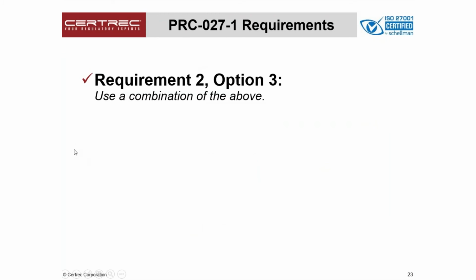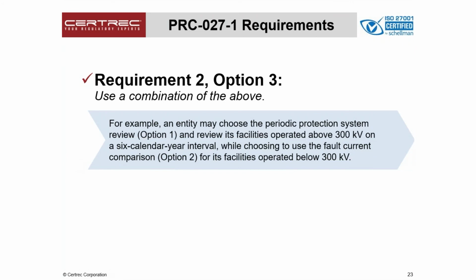Option 3 is to use a combination of the above. So this is an example out of the standard. You may have a facility that connects into 2 different voltage levels. You may have one that ties to a 300 kV or above, like a 345 kV system, and you may want to use option 1 for it, which you can. And then you may have one that ties into, say, a 138 kV or something below 300 kV. You can use the fault current method. So you can choose a combination of these types of studies that you want to follow.